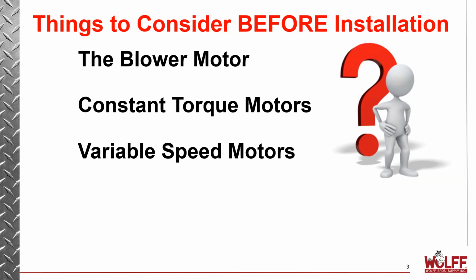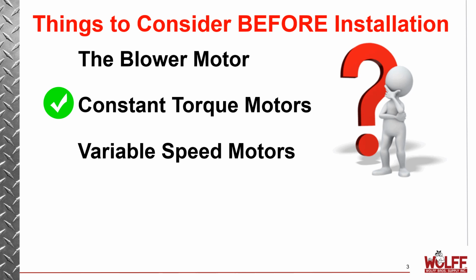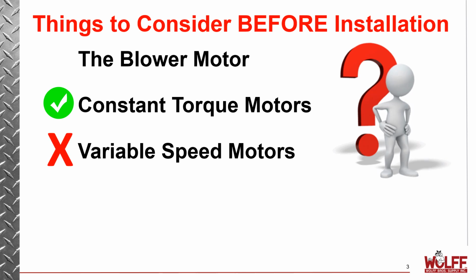The main thing to consider before installation of a twin system is what kind of blower motor the furnace has. Nowadays you have a constant torque motor or you have variable speed motors. If your furnace has a constant torque motor, you're in good shape. If your furnace has a variable speed motor, you cannot use it. Variable speed motors don't work in a twinning situation just due to their ability to run in reverse.